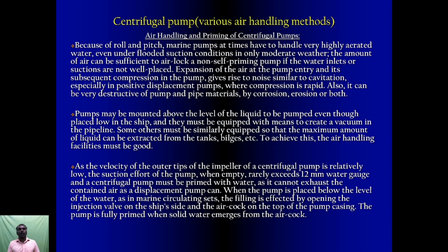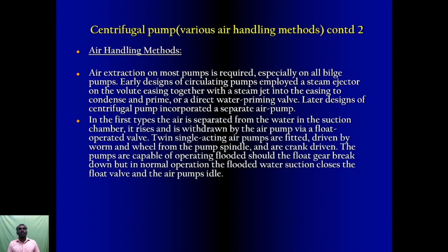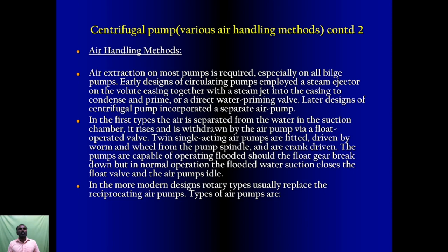When the pump is placed below the level of the water, as in marine circulating sets, the filling is effected by opening the injection valve on the ship side and the air cock on the top of the pump casing. The pump is fully primed when solid water emerges from the air cock. Then, various air handling methods. When we consider the centrifugal pump, priming is the most important method to clear the vacuum.